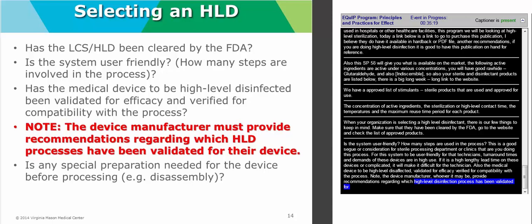All right, so now we'll cover the Bible, so to speak, for high-level disinfection and chemicals, which is the ANSI/AAMI ST58. It's the national standard, and it provides guidelines for the selection of liquid chemical sterilants or high-level disinfectants, also gaseous chemical sterilizers that have been cleared for marketing by the Food and Drug Administration for use in hospitals or other healthcare facilities. So in this program, we're going to be looking at high-level disinfection and chemical sterilization today.